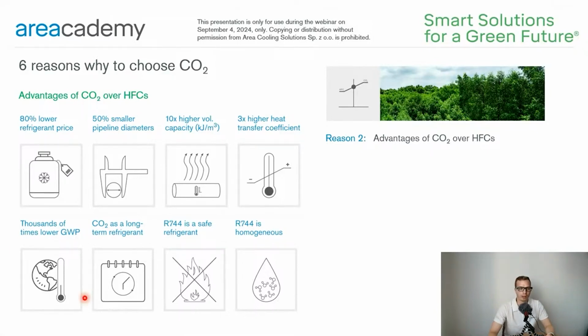CO2 also has a high potential for heat recovery. The discharge temperature can easily reach over 100 degrees Celsius. We can use the rejected energy to heat up, for example, the domestic water. Due to its very good thermodynamic properties, it brings energy savings. There are installations where it has been confirmed that by changing the system from R404A to CO2, the energy consumption has been reduced by around 30%.